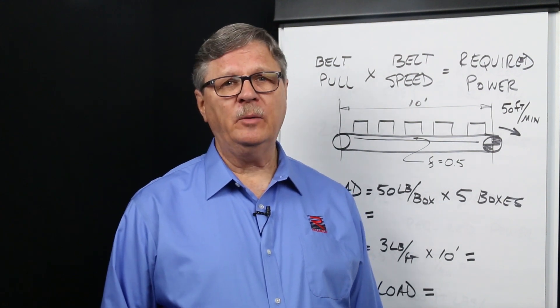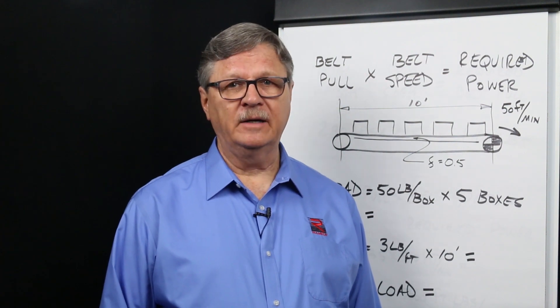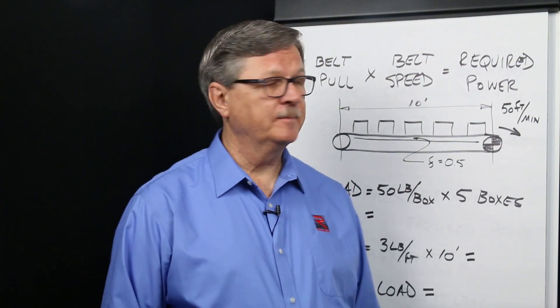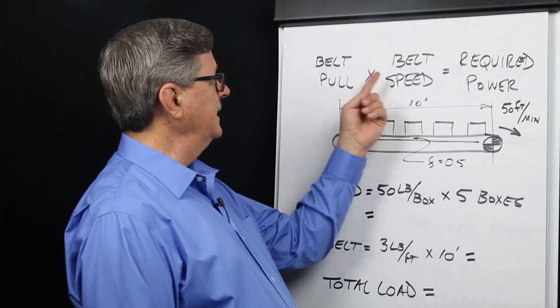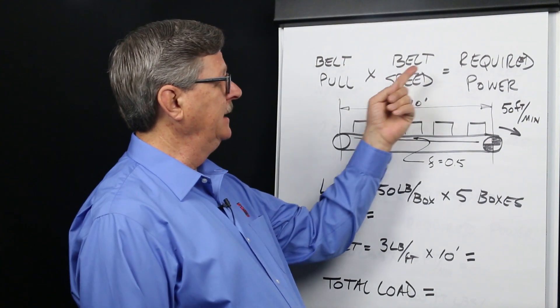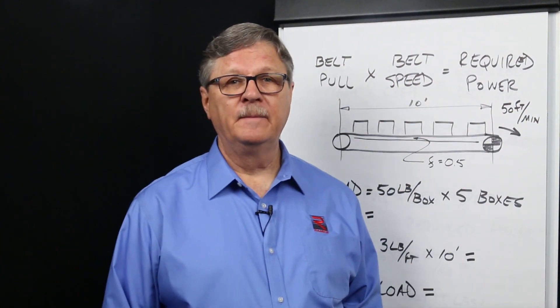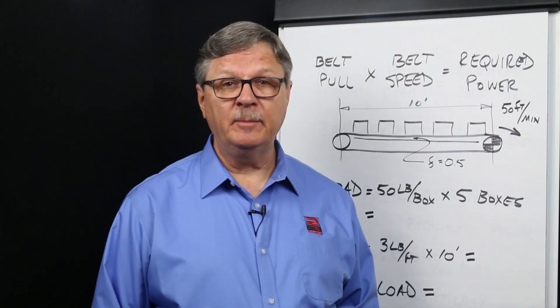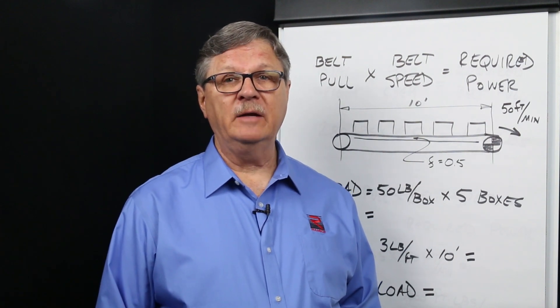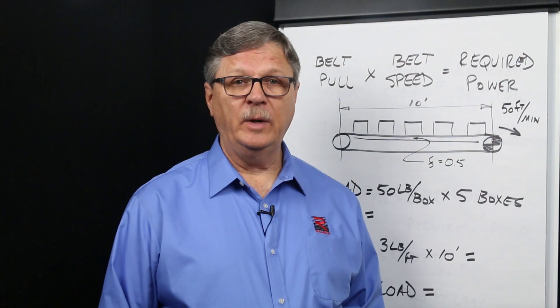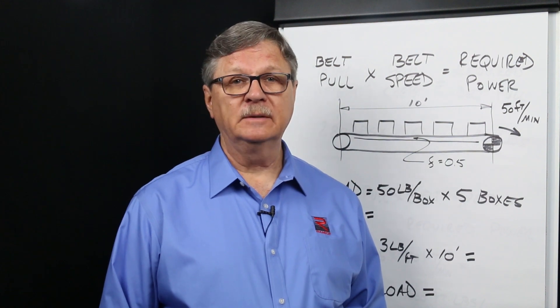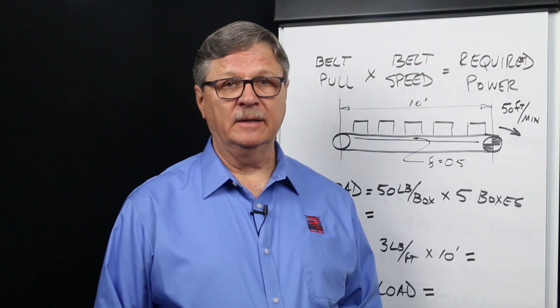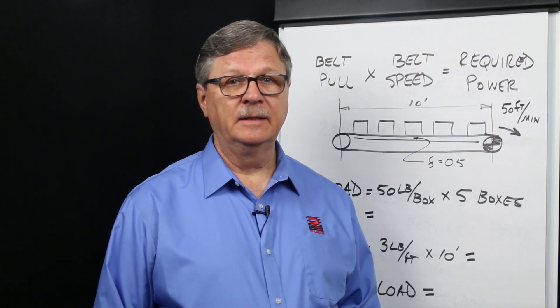We know that the power required to move a load on a belt conveyor equals belt pull times belt speed. The belt pull required to move packages on a slider bed conveyor equals the total weight of all packages plus the weight of the belt, times the coefficient of friction between the bottom of the conveyor belt and the top of the slider bed.